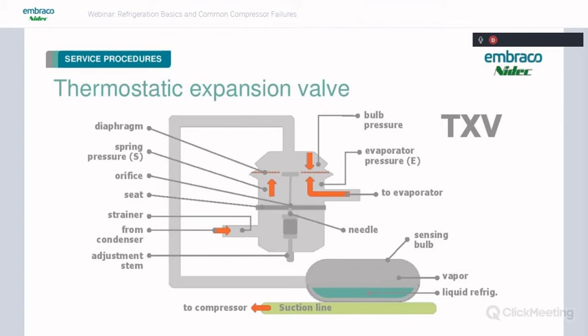This senses the heat load that's on the evaporator, and the higher the heat load, the more it's going to increase the temperature, and then cause the refrigerant that's in the bulb to vaporize and put more pressure on the top of the TXV valve on the bellows, which is going to cause it to open. We have one opening force, which is the bulb pressure, and we have two closing forces, spring pressure, and evaporator pressure trying to close it. And so here, this is basically the throttle of the TXV valve, the vapor bulb, causing it to open or close and meter the correct amount of refrigerant to the evaporator.